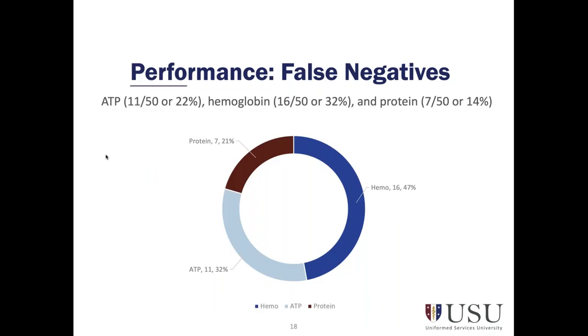Throughout the 3 rounds of testing, all systems yielded false negative results, even when there was observable content on the sample swab. ATP had 11 out of 50, hemoglobin 16 out of 50, and protein 7 out of 50. These findings are significant and concerning because they show the limitations of each system in not capturing every form of bioburden. Educating the staff on how to react to false negative results is crucial to ensure surgical instruments are entirely clean prior to packaging and sterilization.